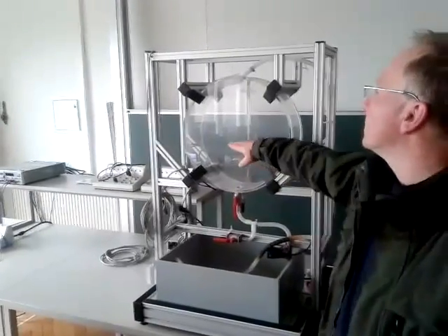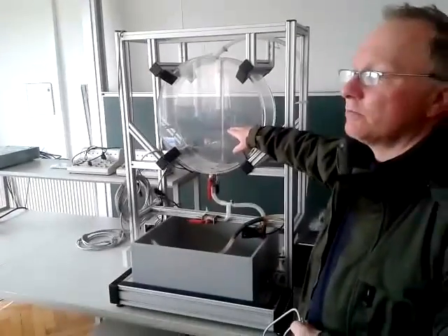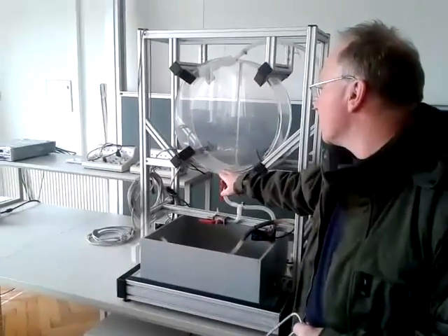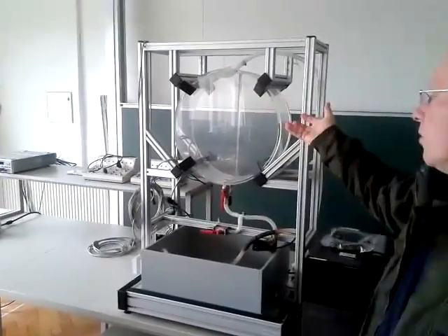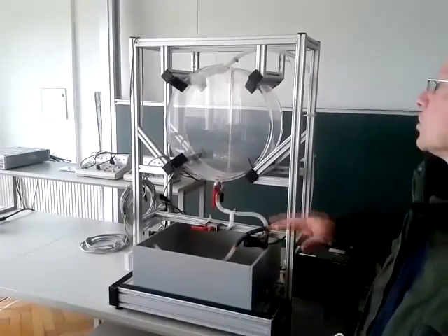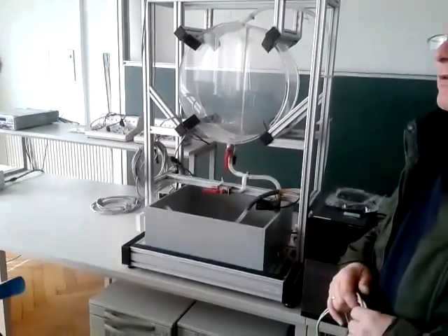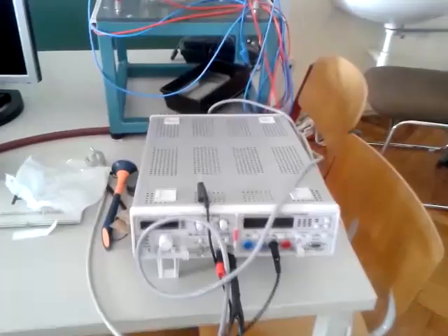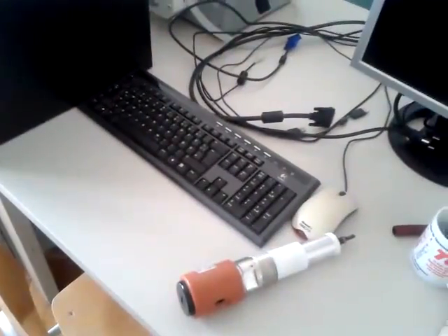And then control the level in this vessel, and in this part it's a nonlinear behavior, because there's another behavior in this part, and in this part. So we also have the problem: do we use a PID controller or fuzzy controller, or switch depending on the level, different sets of the PID controller? We make the speed measurement and control.